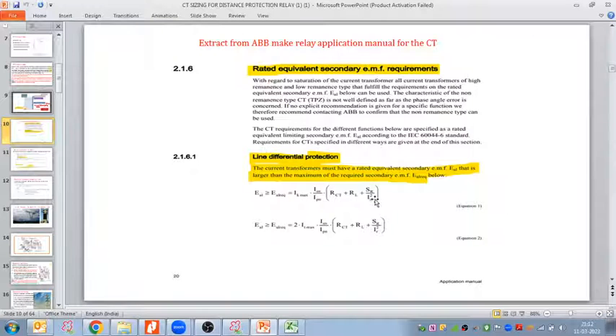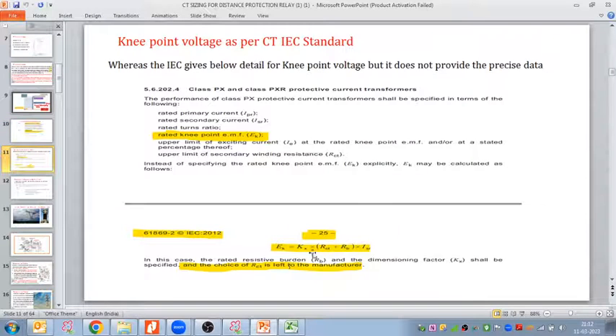They have given equation 1 and equation 2. Both equations we have to solve. For both equations we have to calculate the knee point voltage, and the maximum of the two we have to decide for the CT knee point voltage or the secondary EMF, right? So this we have seen. This is the formula given by the relay. Another, if we want to calculate with the help of the IEC standard, we can follow this formula.